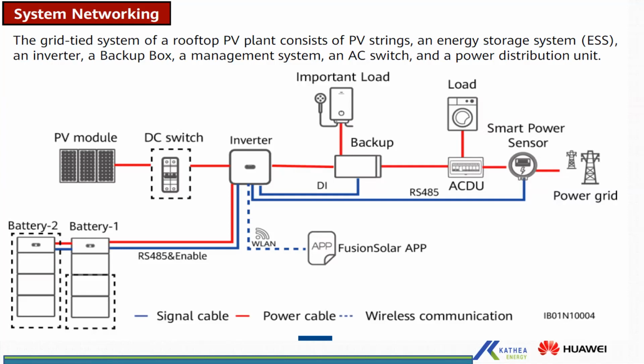And then the AC line from the grid, you would need to install a power meter. So this is a system that works with a grid, so there is need to monitor our export. In regions where you're not allowed to export, you need to monitor your grid tie-in point, so that you won't feed back to the grid. Your meter is supposed to be installed right at your mains incomer, because it is the one which generates the set point for the inverter to produce, right?